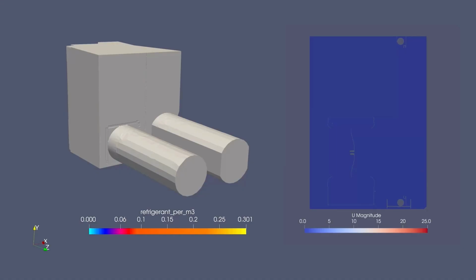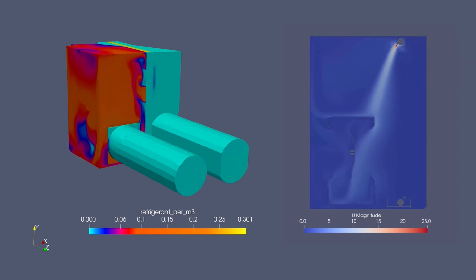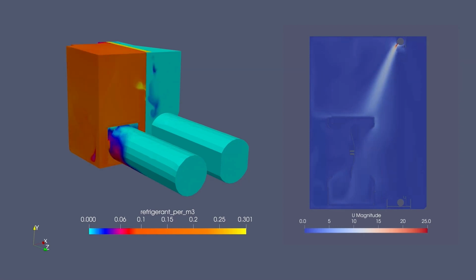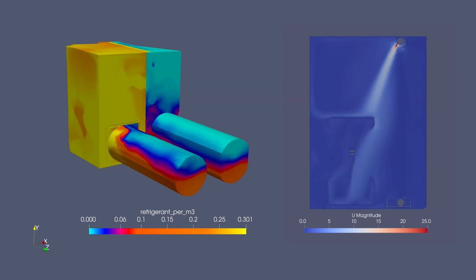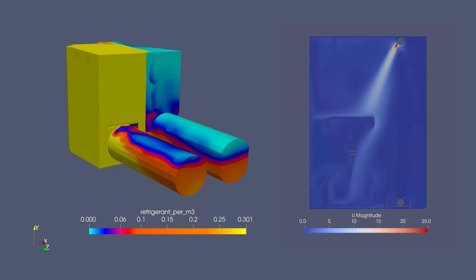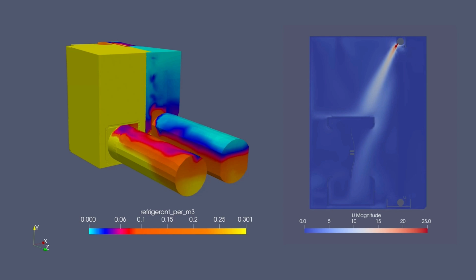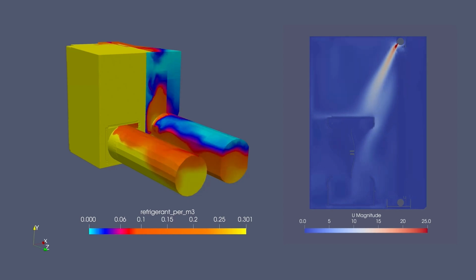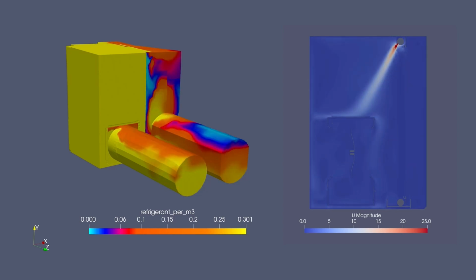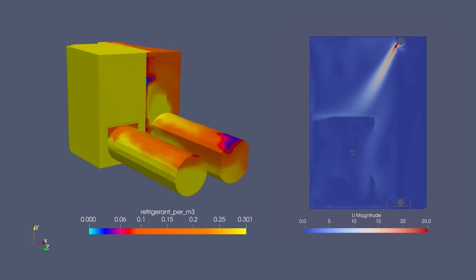Then, we used flow modeling software to run hundreds of possible leak scenarios, different locations, directions, and flow rates. We look at where the simulated refrigerant collects in the system. What you are seeing here is a simulated leak scenario in a package system. We use these simulations to pick a location inside the cabinet where a sensor can detect a leak before a flammable concentration occurs. We then verify this location in tests with real equipment and refrigerant.